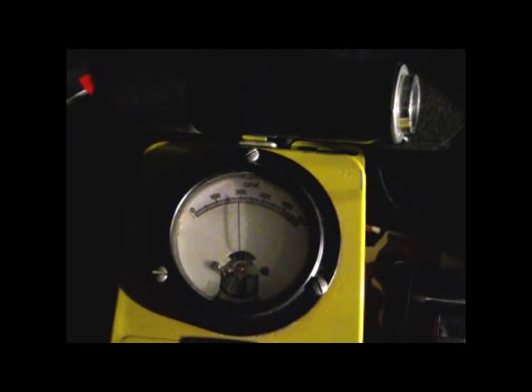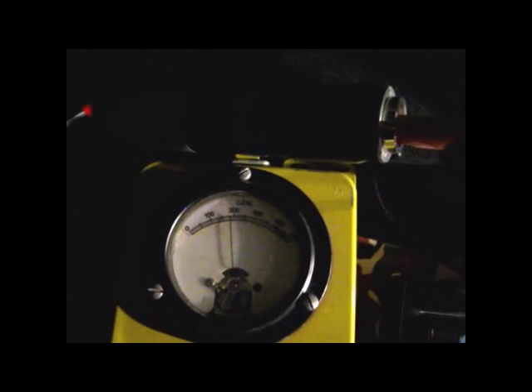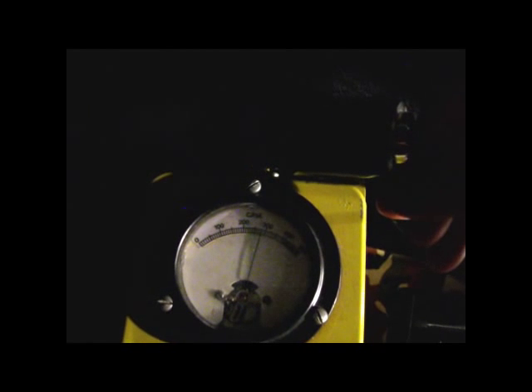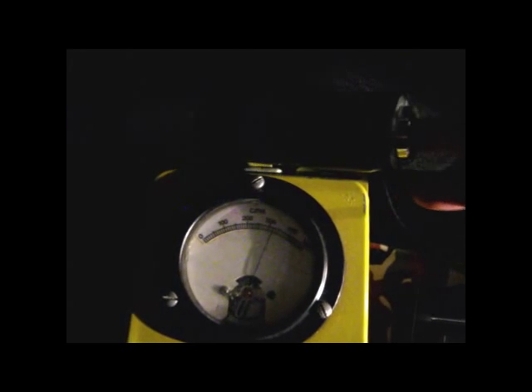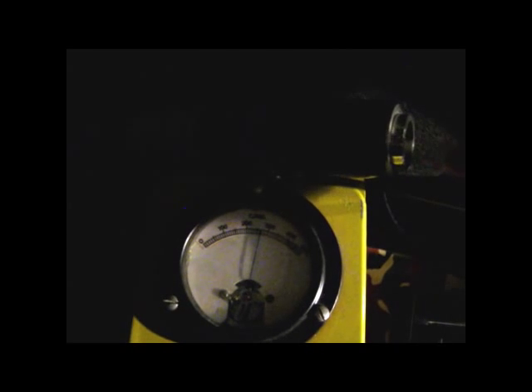What's also interesting to see is with the scintillation counter, the well-hole detector — you can see if I stick in an uncontaminated finger, it probably picks up nothing. Contaminated finger — that was just in there for a short time — picks up something. And a badly contaminated finger, that's going to be a lot of counts.